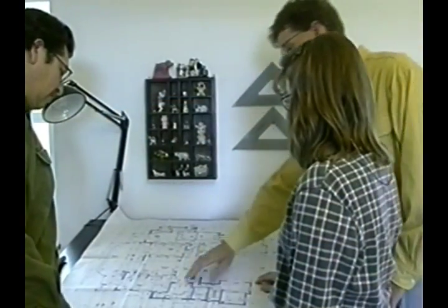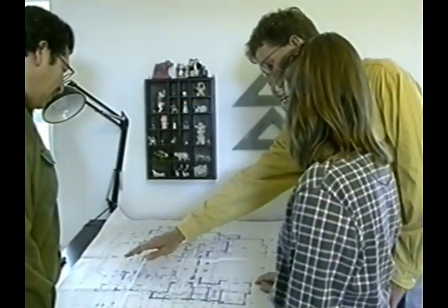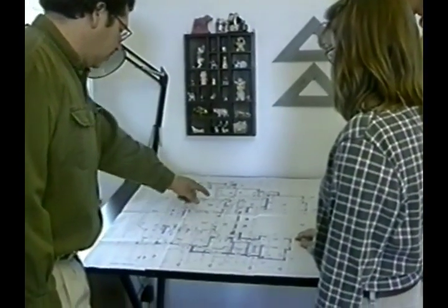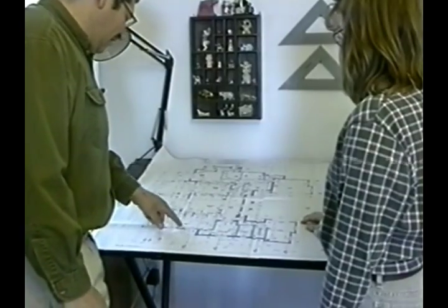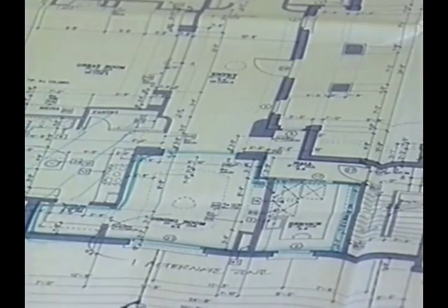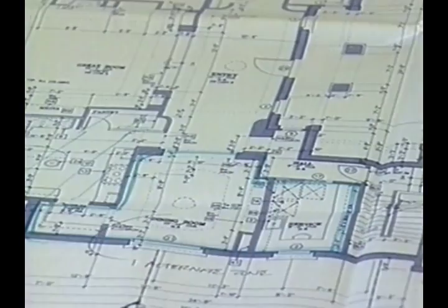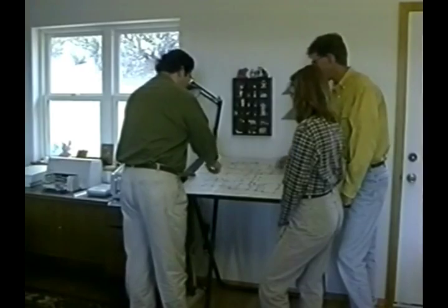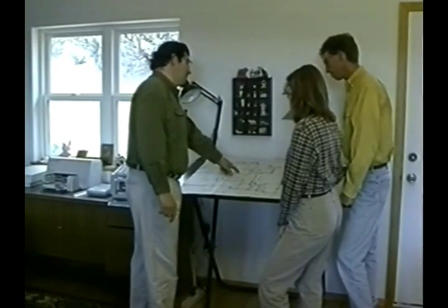To determine the amount of heat required to provide comfort in a room or a house, it is necessary to calculate the amount of heat lost according to the coldest day. A room-by-room analysis must be done to ensure the proper radiant design. The heat loss from an area must be replaced by heat from the floor. Do not include cabinet areas or other areas that do not generate heat. It is very important to provide the program accurate room measurements to assure the proper tube size.